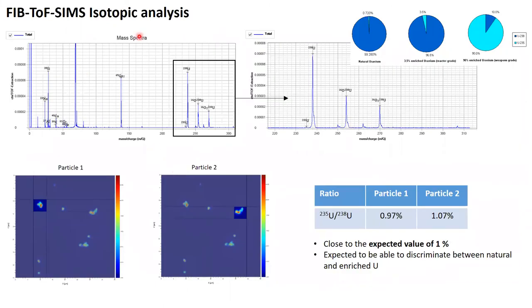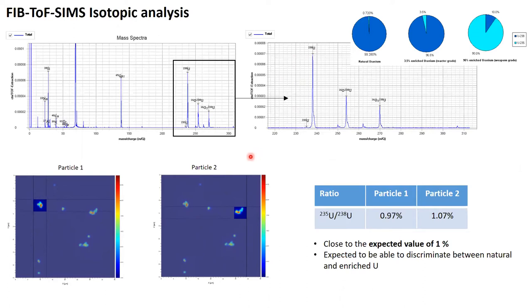In another isotopic analysis example, we looked at very small uranium particles, on the order of just a micron, and analyzed individual particles to determine their ²³⁸U to ²³⁵U ratio. Analyzing a standard with about 1% ²³⁵U to ²³⁸U ratio, we got very close to the expected value — giving us confidence to use the instrument for basic isotopic ratio analysis of uranium. This can also be combined with high resolution imaging and EDS.